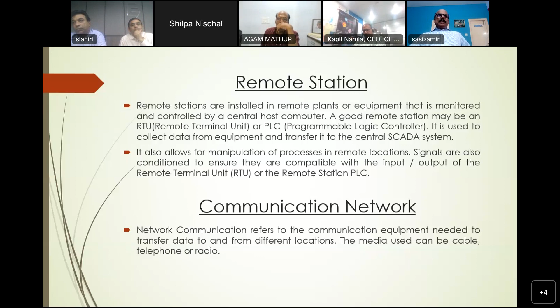The central monitoring system is the master unit of the SCADA system. It is in charge of collecting information collected by the remote stations and producing the actions needed for each event detected. A human-machine interface program will run on the CMS computer. A plot diagram of the entire plant or process can be displayed on the screen for easy identification with the real system. So each input and output point of a remote unit can be displayed with an appropriate graphical representation and input-output readings. Then there is the database for analyzing and processing the data gathered by the SCADA system.